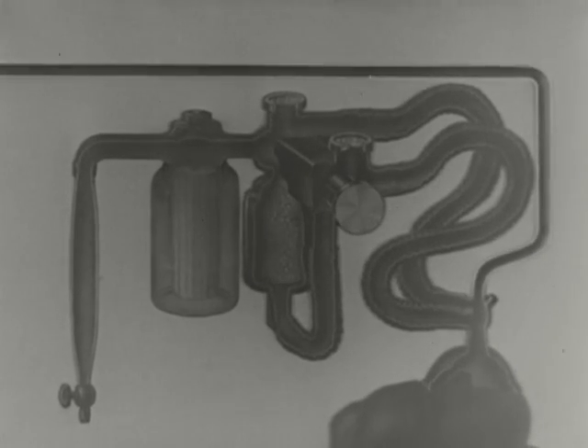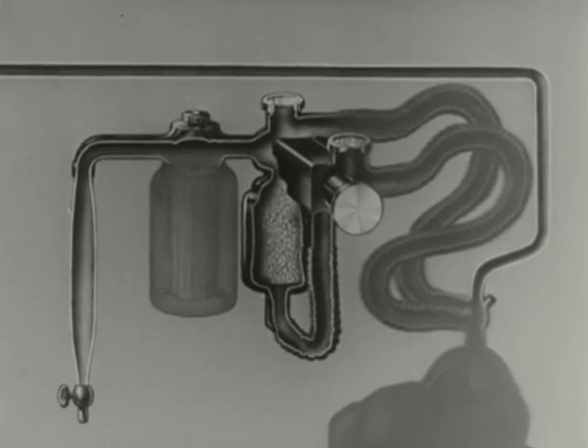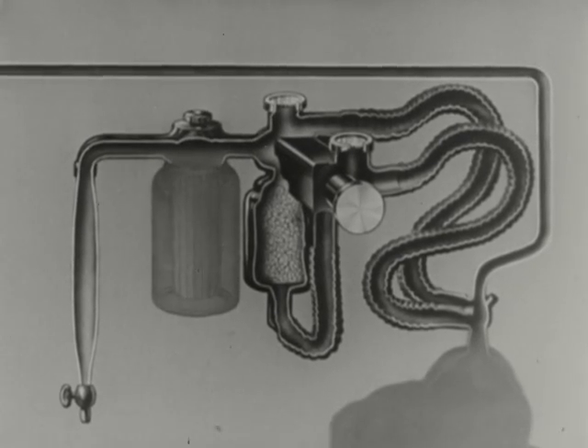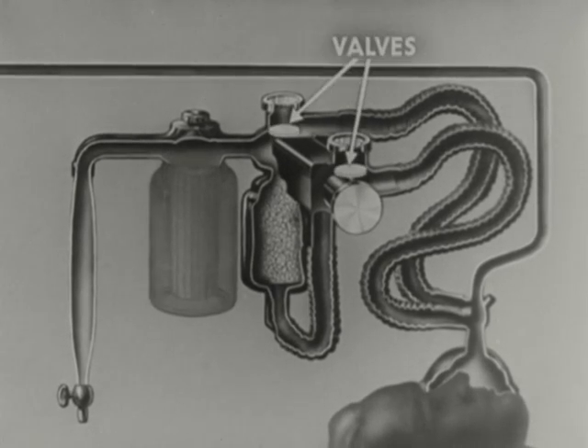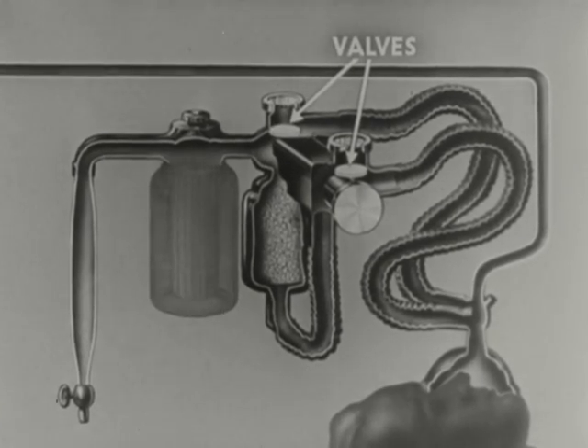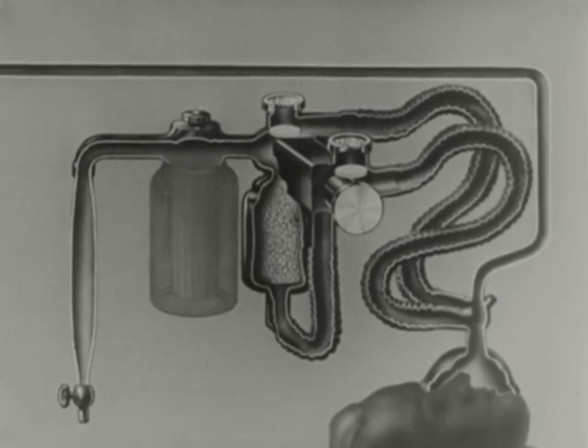The alternative method is called closed circuit or two-phase absorption. A narrow bore tube for the fresh gases runs from the flow meters to the Y piece. The rebreathing bag and the canister are attached by two tubes, a corrugated rubber hose, to the Y piece and face mask. At one end of each tube is a directional valve so that the patient expires through one tube and inspires through the other. Various circuits are possible, but this one is common.